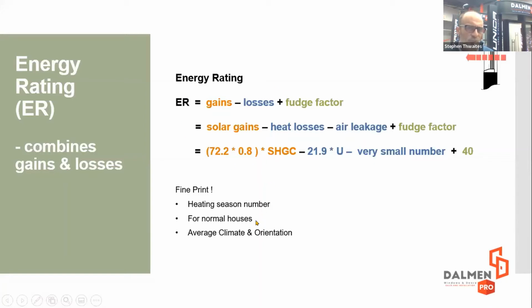This was based on a normal house. This breaks down very quickly - I can't use this in new condominiums where it's floor to ceiling glass. This all works out to be relatively true if you have a normal window area, not an excessive window area. The other thing, and we'll talk about the impacts a little later, it's based on an average Canadian climate, which turns out to be pretty close to Ottawa. So this average delta T, the average temperature difference over the heating season, turns out to be a good choice. But this is the average of north, south, east, west.